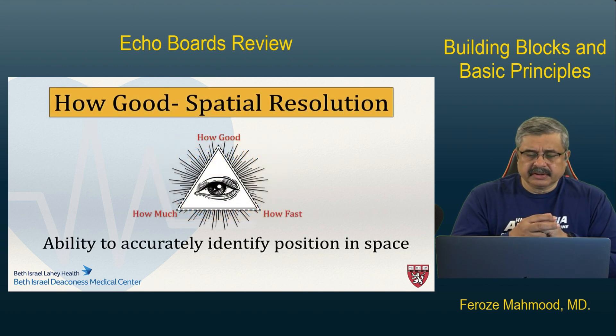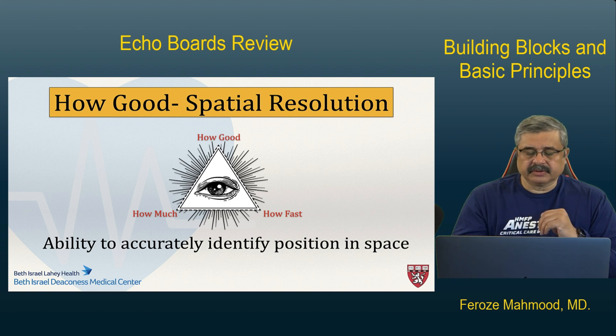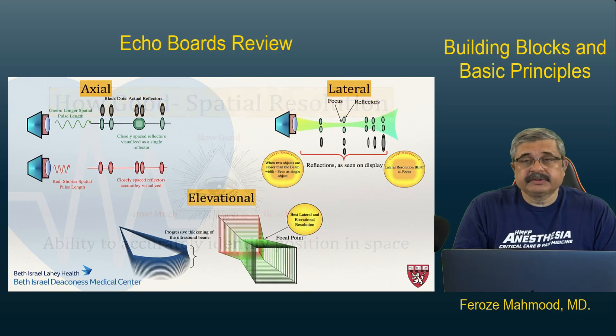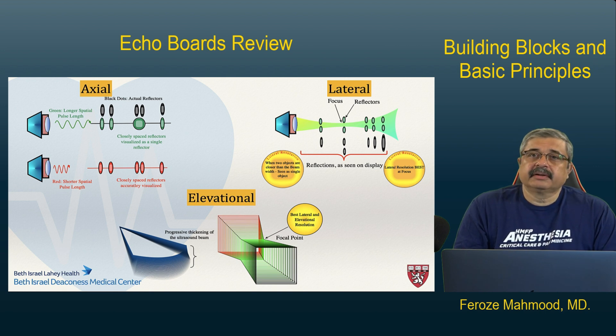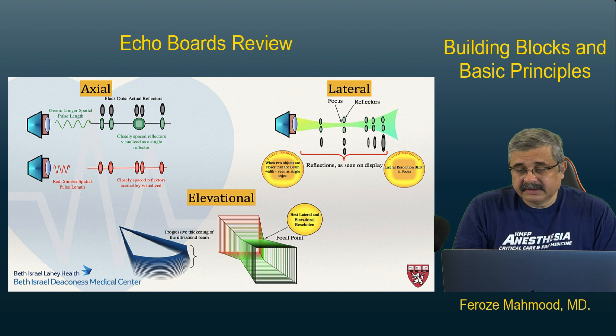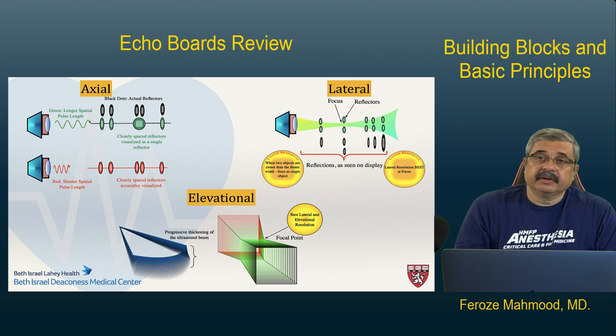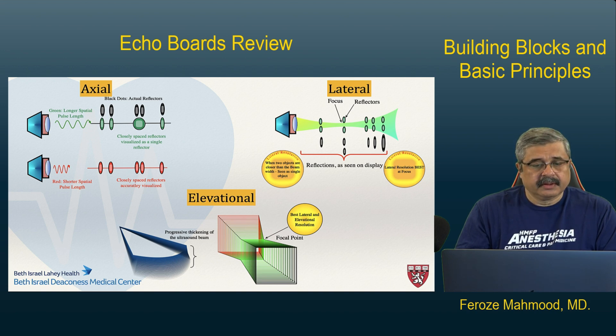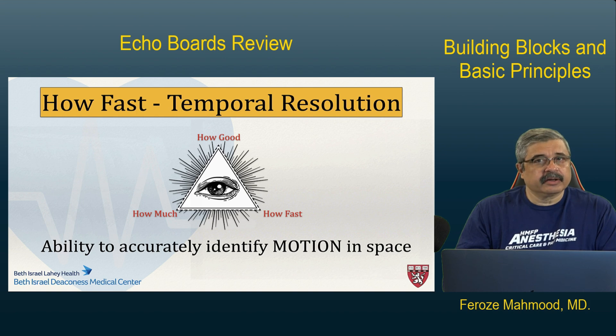Spatial resolution is defined as your ability to accurately identify a position in space. There are three types: axial resolution — your ability to see things front to back, determined by your spatial pulse length; lateral resolution — the ability to identify the distance between two objects lying side by side, determined by the narrowest point of the beam at the focal zone; and elevation resolution — correctly identifying whether a structure is above or below the scan plane. Temporal resolution is your ability to accurately identify motion in space, which is one of the most important things in echocardiography.